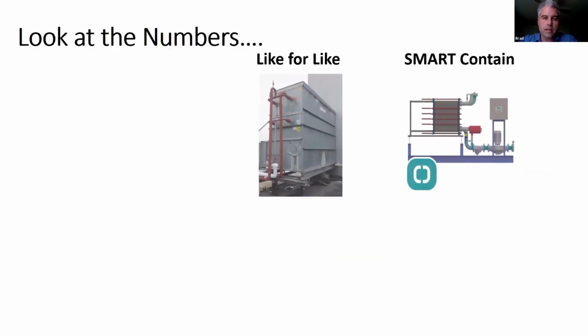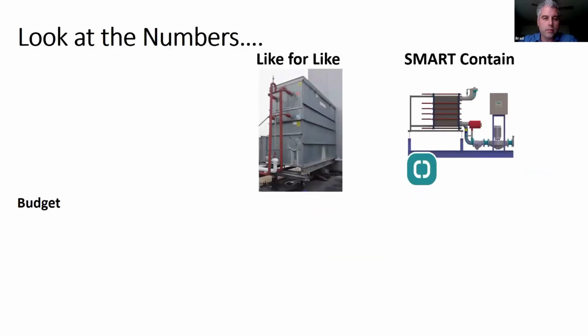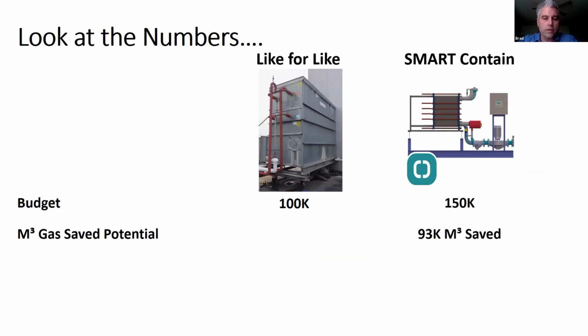Let's take a look at the numbers. Like-for-like, the budget is $100,000. The smart contain is $150,000. But by tapping into the potential and recovering the waste heat, you're now going to be able to save almost 93,000 cubic meters of gas per year. This is based on a single pad arena running 100 horsepower at 3,000 run hours per year.